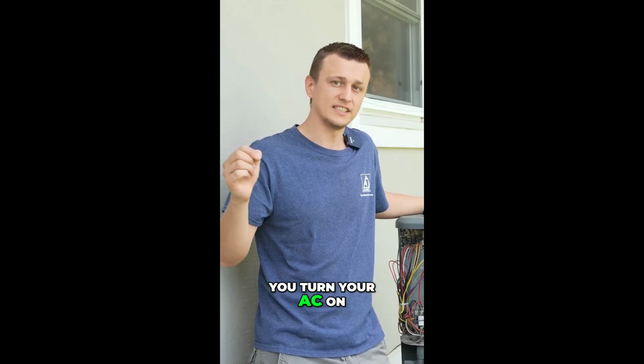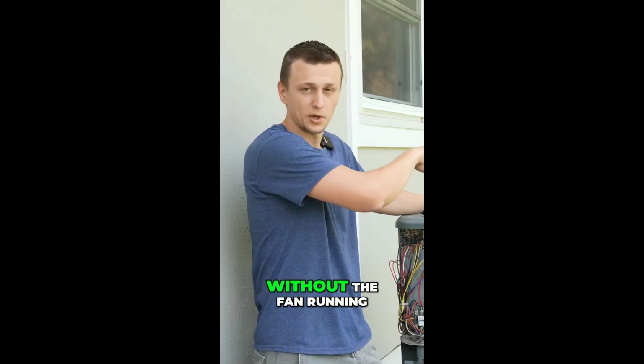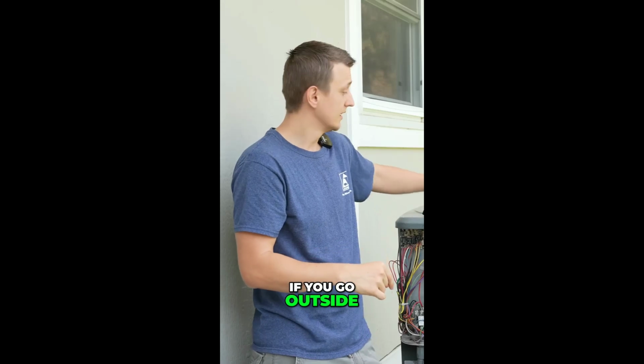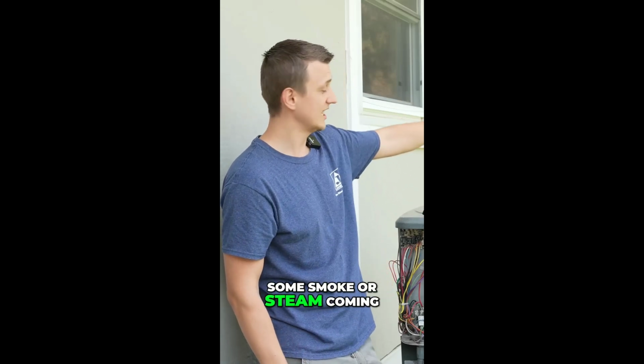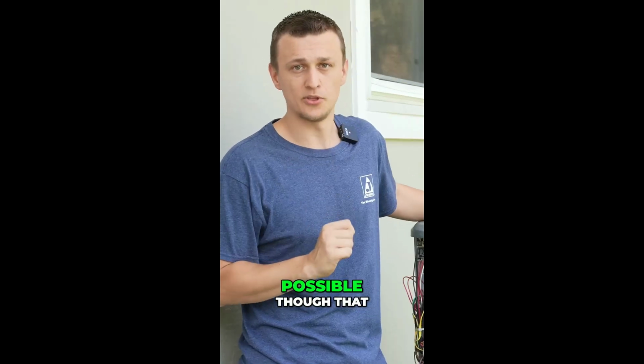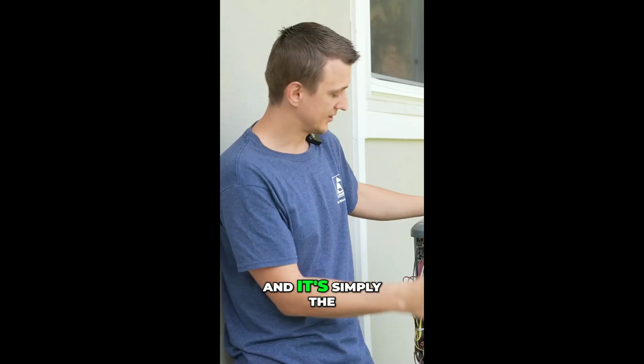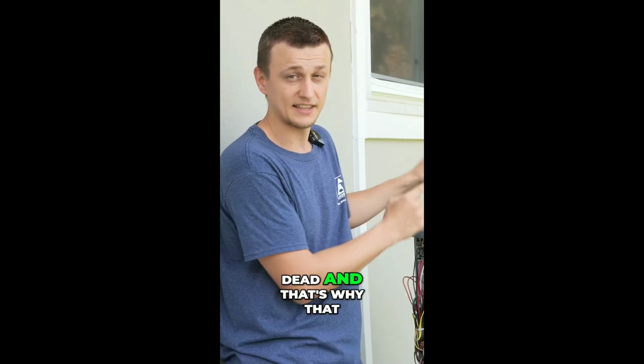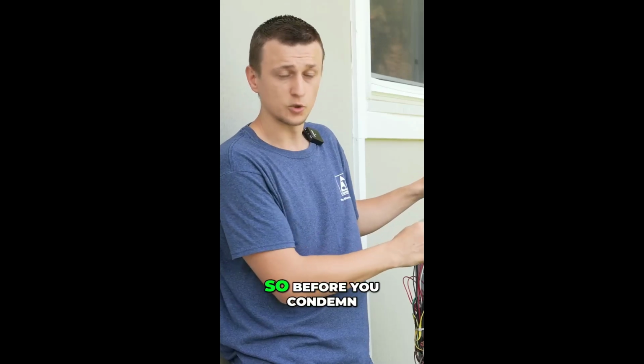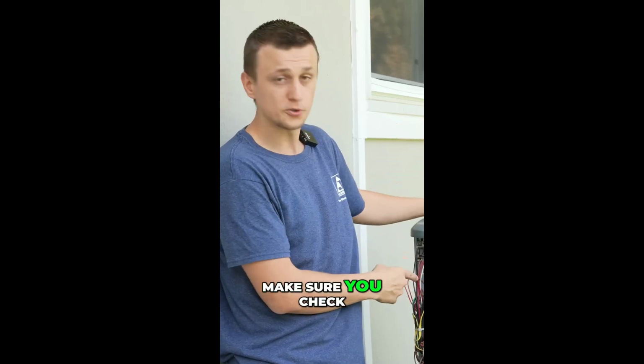Oftentimes, if you turn your AC on and it runs for a couple of minutes without the fan running, if you go outside, you might even see some smoke or steam coming up from your unit. It is possible though that the fan motor is good and it's simply the capacitor that is dead, and that's why the fan motor is not coming on. So before you condemn a fan motor, make sure you check the capacitor.